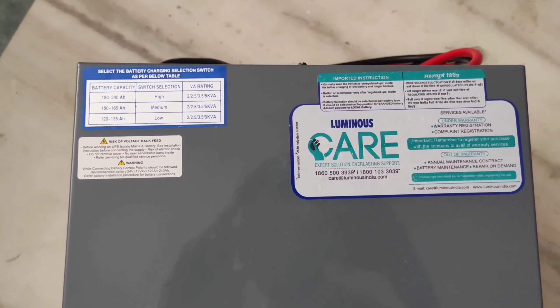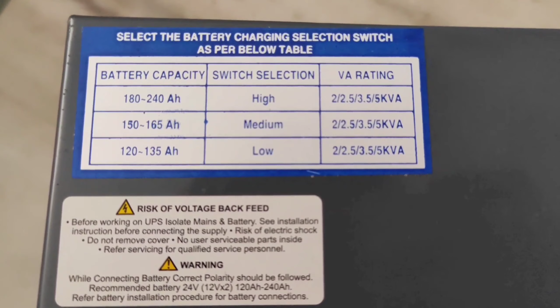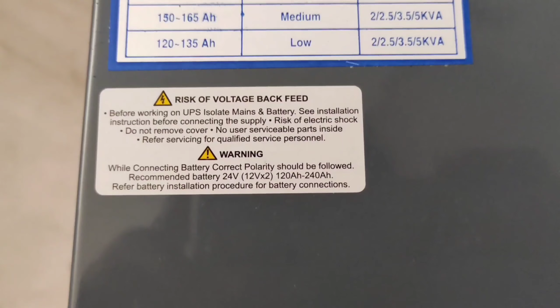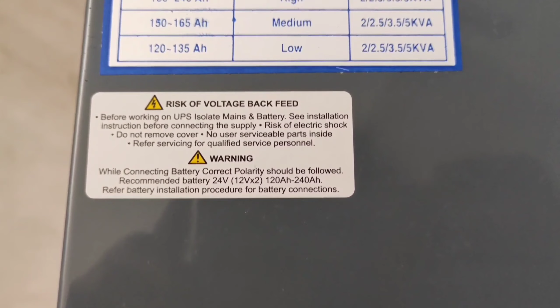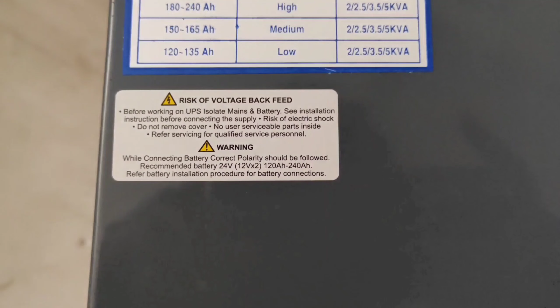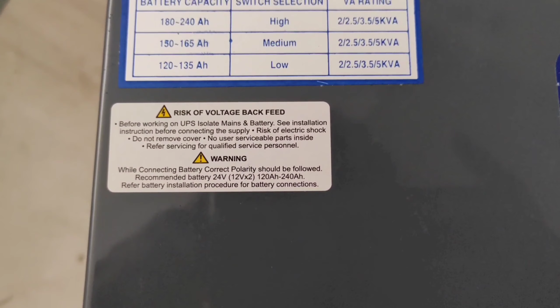Here you can see: select the battery charging selection switch as per the below table. Battery capacity, switch selection, volt ampere rating. Based on the battery capacity, you have to select the charging current, friends. Here you can see volt ampere rating also. Based on this table, you have to select. Friends, here you can see while connecting battery, correct polarity should be maintained. Recommended battery 24 volts, 12 cross 2. That means 2 batteries each of 12 volts connected in series. Battery range is 120 ampere hours to 240 ampere hours.